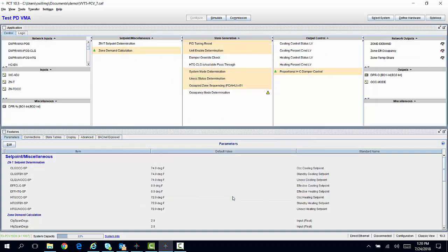So it's sending 3 pieces of information to the RTU and pulling 3 pieces of information from the RTU. And the IP controllers will work with both MSTP controllers and IP controllers peer-to-peer as long as they're on the same subnet.